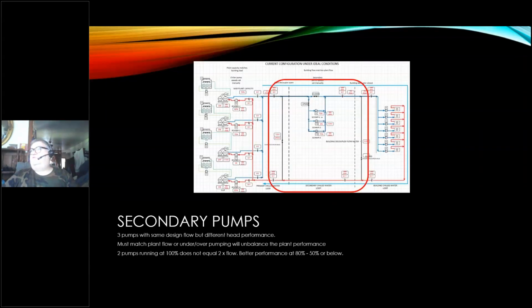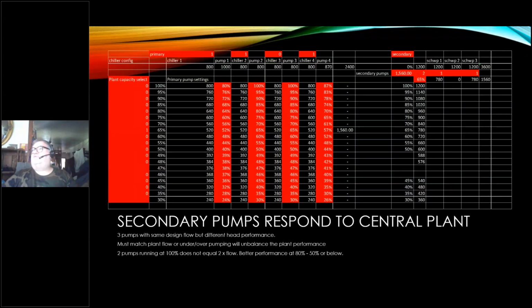Then I have to deal with the secondary loop. These pumps just run to transfer water out of the plant into the building. So again, I have to figure out, I'm operating at 65%. That's where the pumps on the primary, on the chillers, will operate. Then I have to decide how many pumps on the secondary I need, and those end up being, I need to run 2 pumps at 65% in order to come close to matching that flow. What I'm trying to do is match the flow out of the plant to the flow to the building so that I'm not running water back through that decoupler back into the plant.